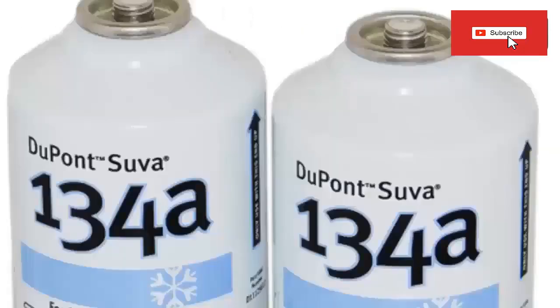2. MO49 is compatible with POE oil. Therefore it is possible to replace R-134a in domestic equipment, without the need to change or modify the length of the capillary tube.